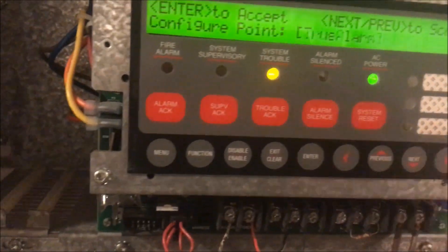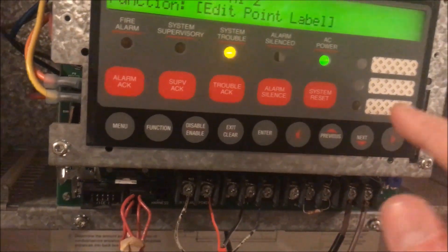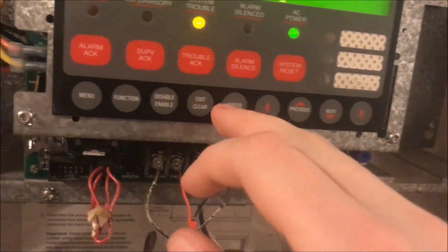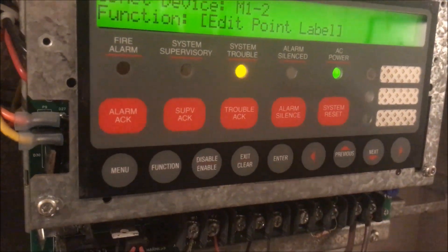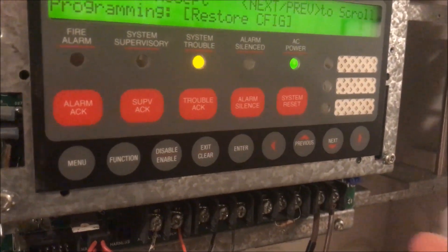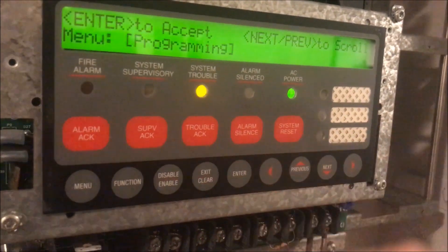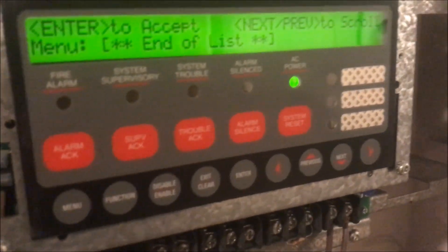In level three programming, you can edit an IDNet point — for example, edit point two. However, you can only change the point label; you cannot add points or delete points in level three, only edit what a point is called. There's also configure points, restore to previous settings, and save your settings. That's it for level three programming, and exiting will clear the trouble condition.